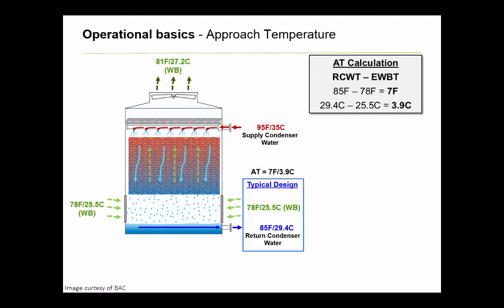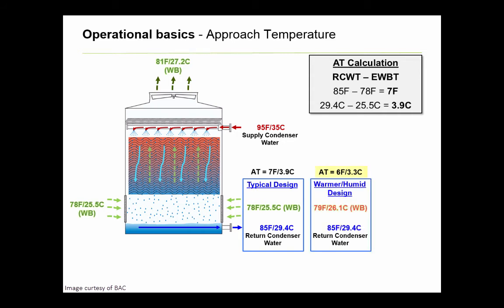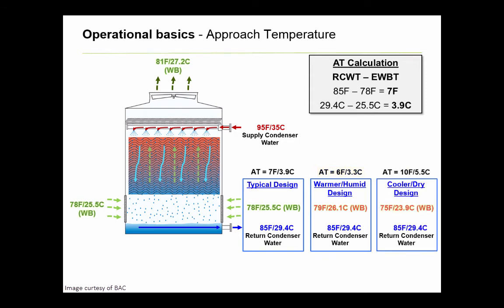But it can move in either direction depending on the climate. In warmer, more humid climates, you will see smaller approach temperatures due to higher wet bulbs. And in cooler, drier climates, you will see higher approach temperatures due to lower average wet bulbs. This is all important information in the design and operation of a chiller plant.